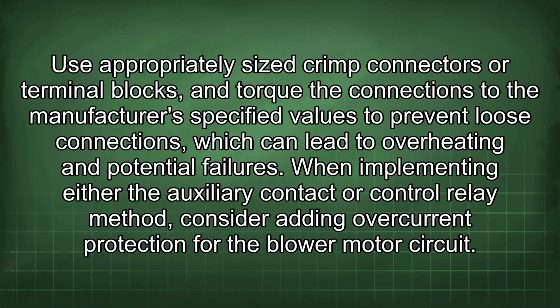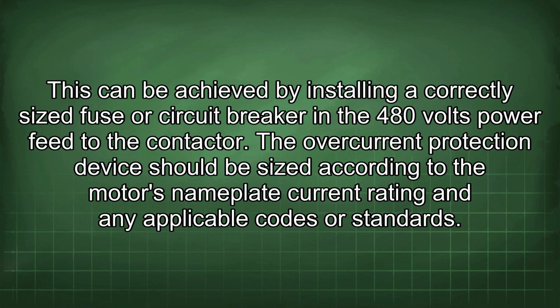When implementing either the auxiliary contact or control relay method, consider adding overcurrent protection for the blower motor circuit. This can be achieved by installing a correctly sized fuse or circuit breaker in the 480 volts power feed to the contactor. The overcurrent protection device should be sized according to the motor's nameplate current rating and any applicable codes or standards.